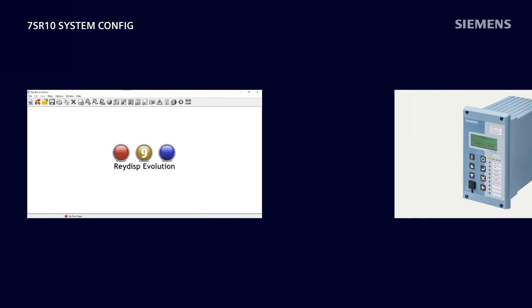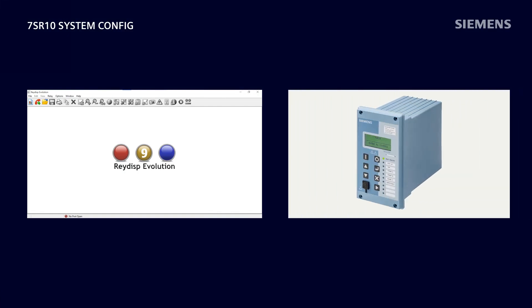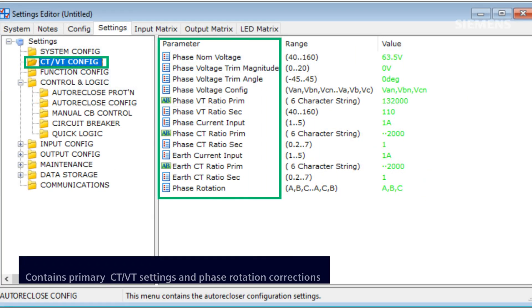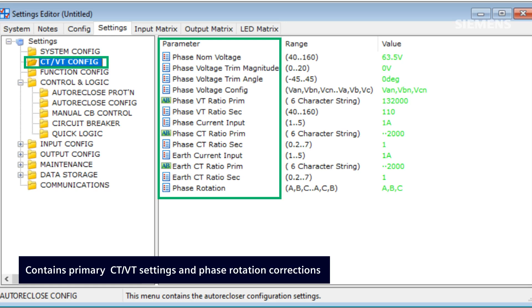The Reyrolle 7SR10 device parameters can be configured either via the Reydisp Evolution software or directly through the device's HMI. In this video, we will explore some of the parameters found under the CTVT config section. This menu includes configurations for the primary current and voltage transformer settings, as well as adjustments for phase rotation corrections.